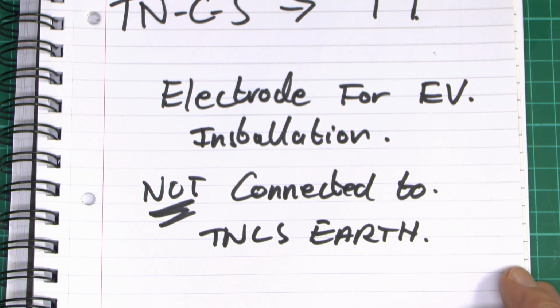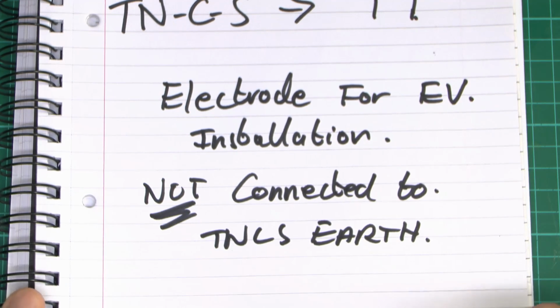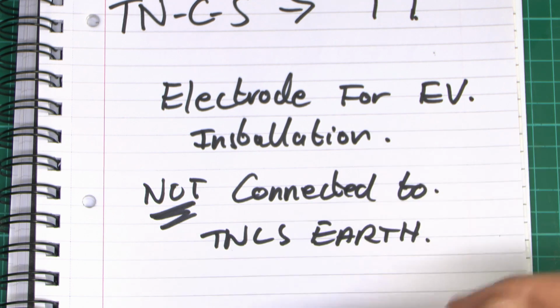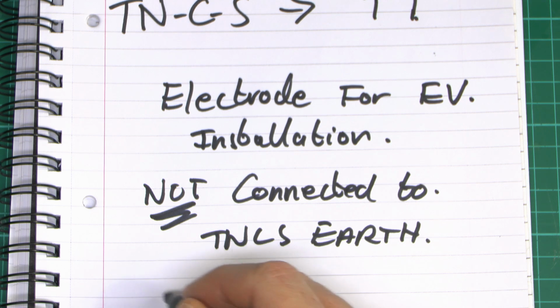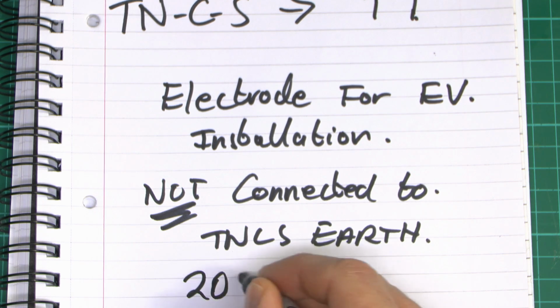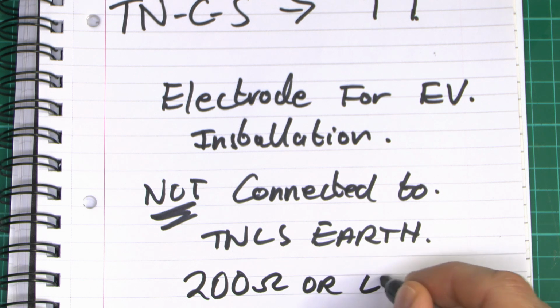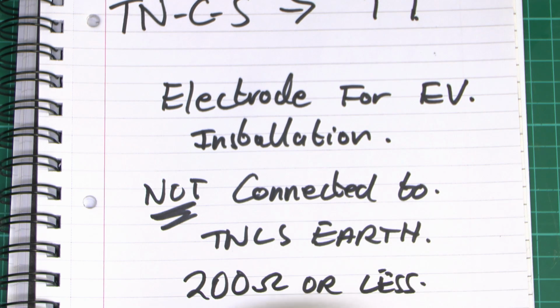So an entirely separate installation, an earth rod specifically for the earthing for the electric vehicle charging equipment, and you're definitely not going to connect it to the TNCS earth in any way, because again that just comes back to that same problem we had before, where you have to get it in the ridiculously low 2 or 3 ohms area. And if you do it as a TT, of course it would have an RCD on there, but it's just then the same as any other TT installation.